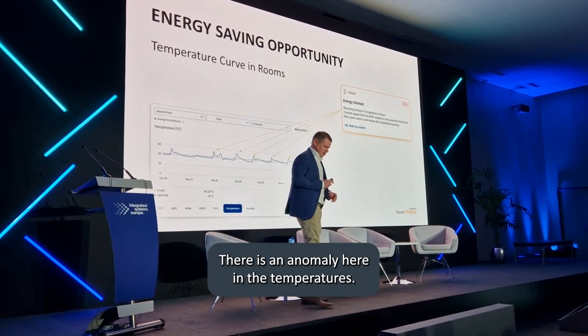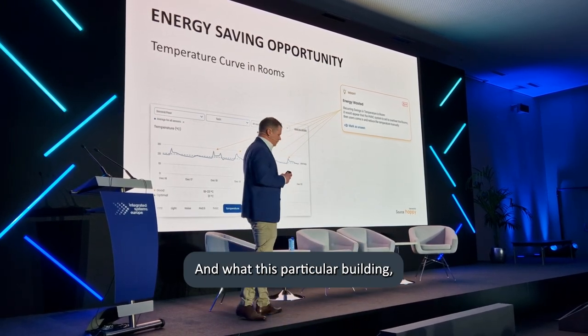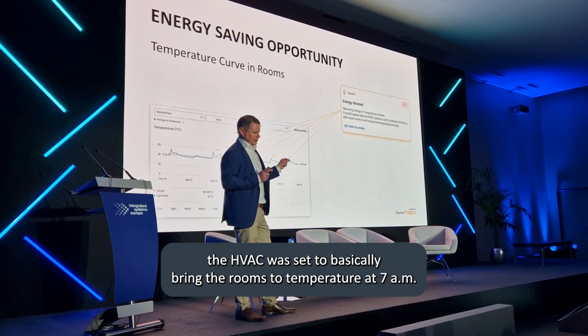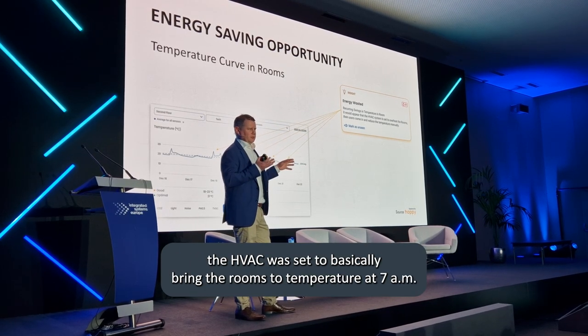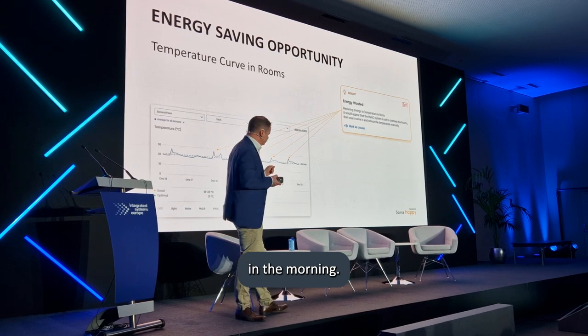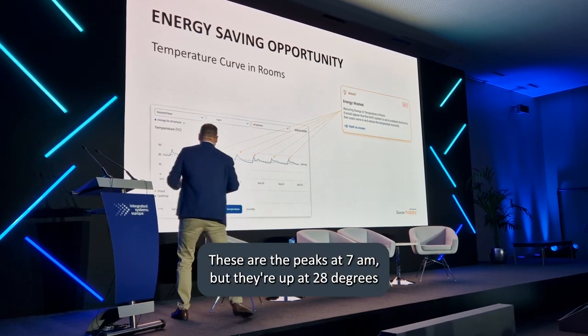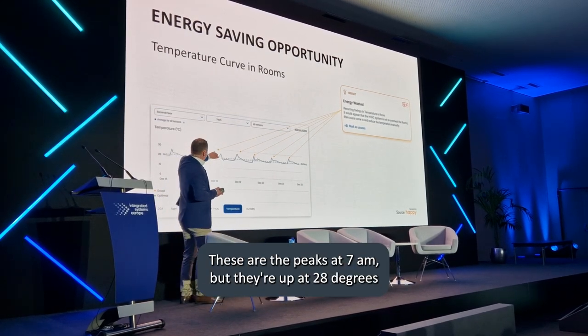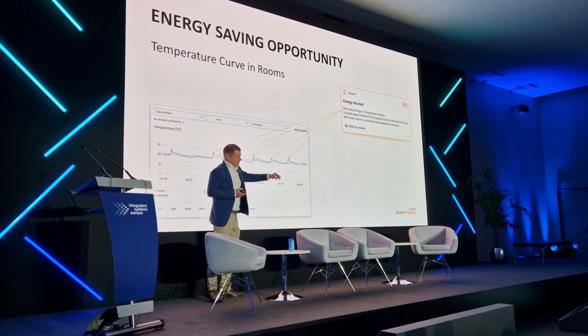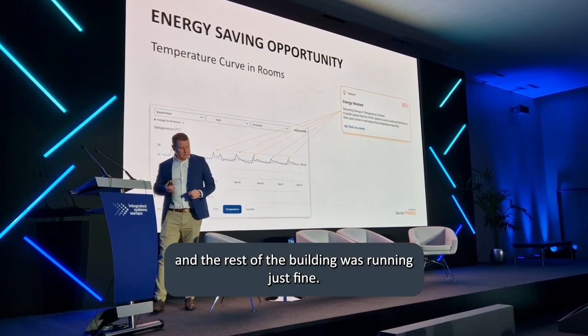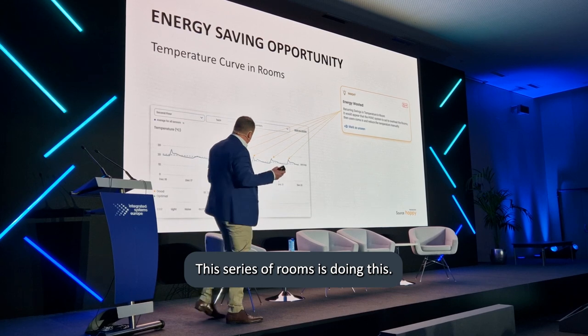In this particular building, the HVAC was set to bring the rooms to temperature at 7 a.m. That's what you see here - these peaks at 7 a.m., but they're up at 28 degrees. The rest of the building was running just fine. This series of rooms was doing this.